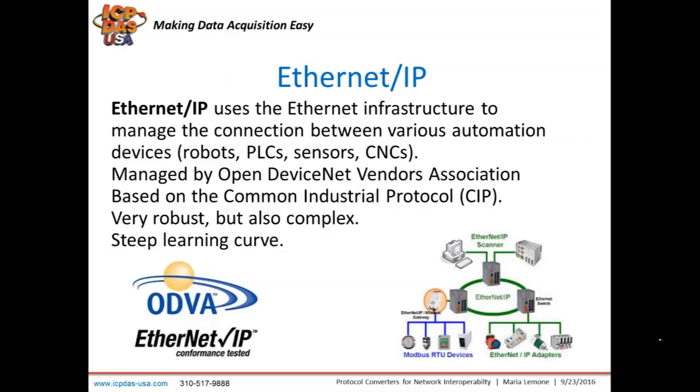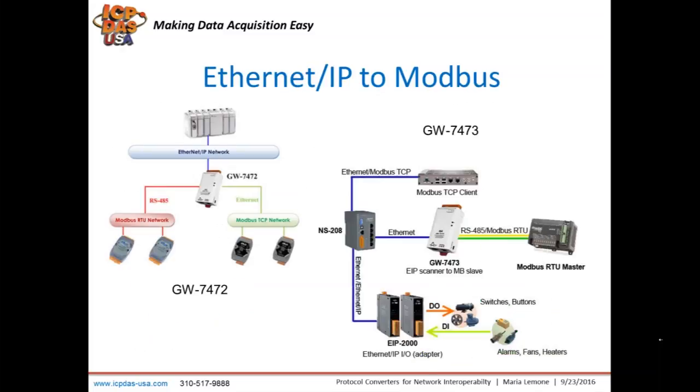Modbus RTU can be transmitted over cables up to 1.2 kilometers or about 4,000 feet and can be extended using repeaters. But you may need to monitor a Modbus device over the internet in another location. An example is in a building where there is already an Ethernet network. Cabling is available and you need to use serial-based devices. In both cases, the solution will be converting Modbus RTU to Modbus TCP, using the example of the TGW series shown in the picture.